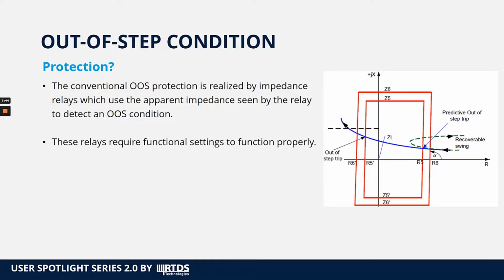For this, the impedance-based protection devices require settings in order to function properly. And to compute these settings, the network should be well studied. To compute these settings for the impedance-based relays, we need to thoroughly run network simulations, and this is very time consuming, and the network should be well known for the settings calculation.